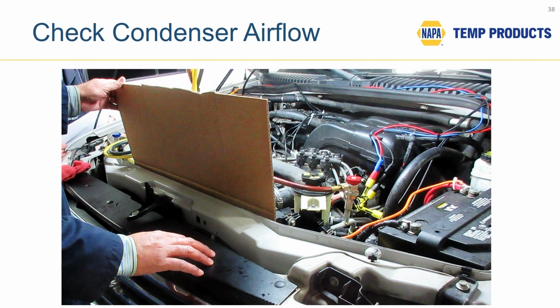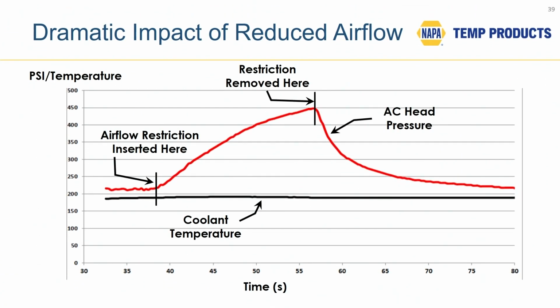This is an experiment we do here when we do hands-on class at our training center. I'm sliding a piece of cardboard down in front of the radiator behind the condenser, in other words, blocking airflow through the condenser. You can see that in about 20 seconds, high side pressure went from about 220 psi to almost 450 psi. Look at the black line, which represents engine coolant temperature. This is the data exported right from the scan tool. Engine temperature didn't change at all. In fact, it went down a couple of degrees when we took the heat load of the condenser off the radiator, but high side pressure literally doubled.